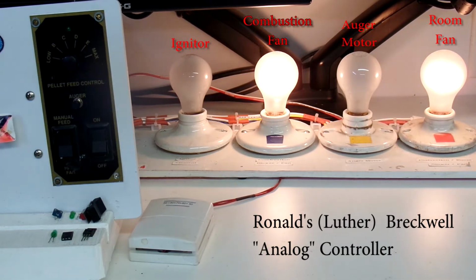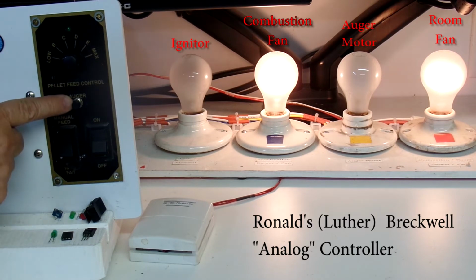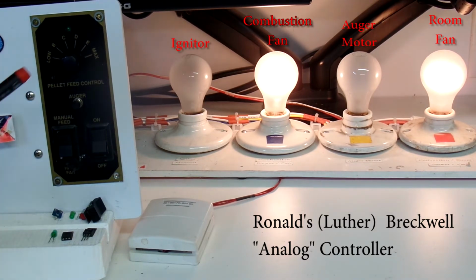The next thing I'll do is I'll set the controller into automatic mode. To do that, I need to press the auger button here. When I do, a few things will happen of note. First, we'll see the green light at the top here come on. That'll tell us that the controller is in automatic mode. Next, we may get a quick cycle of the auger motor itself. You'll see the light come on and you may see the auger motor spin itself.